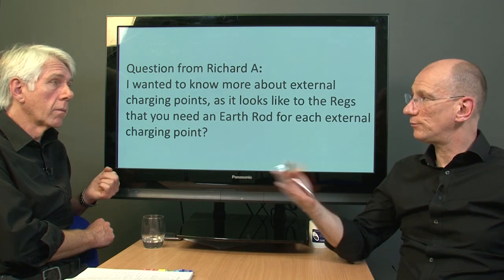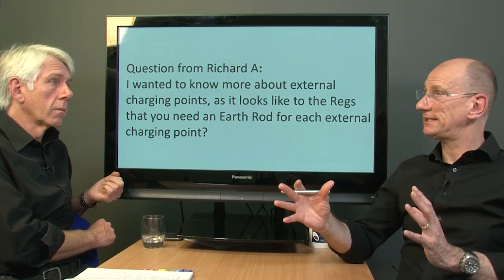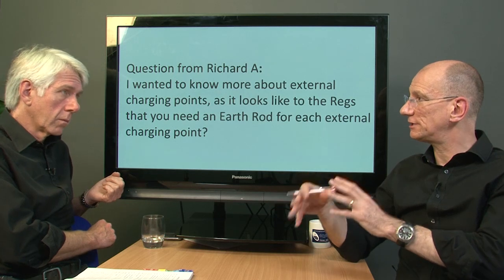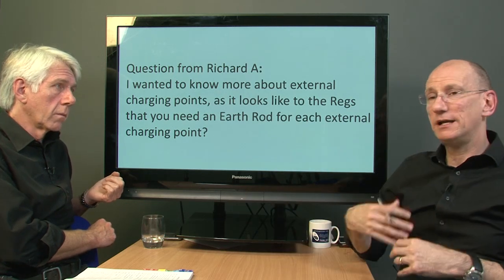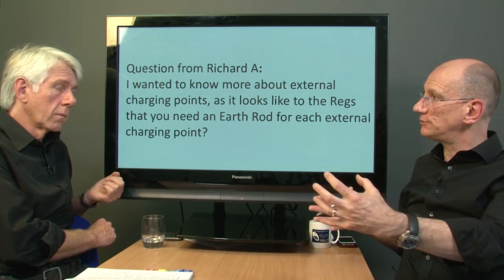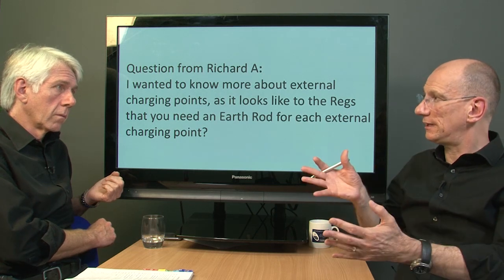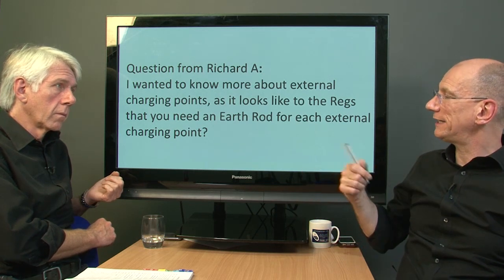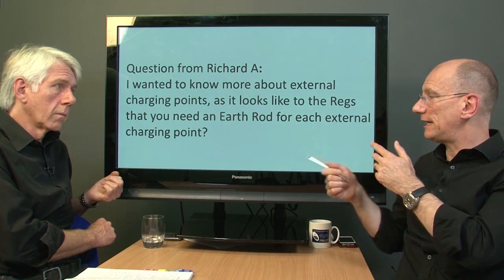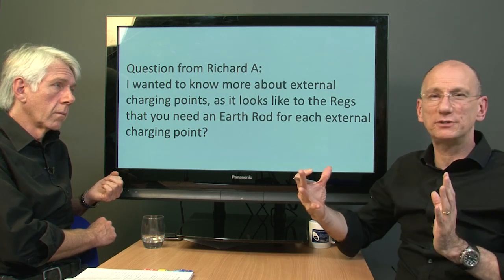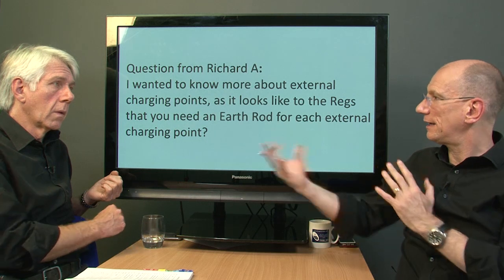Yeah, you don't. The bits we covered: if it's TN-C-S, it's at the main earthing terminal as a supplementary. And if you were going down the route of separating those to not change the risk but eliminate it or deal with it, you'd make it TT, then you would need an earth electrode. So I've given you both scenarios to differentiate the two.